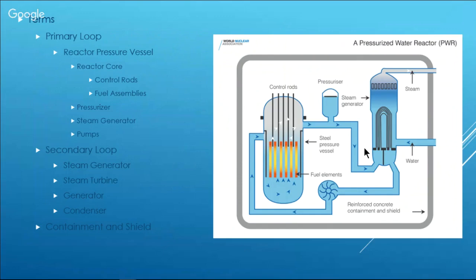So let's say, for example, you have a particular set of control rod positions. You leave them fixed. When you pull heat by pulling off steam, the material going back into the reactor changes density, you increase the reactions, and you increase the heat coming out of the reactor. So by itself, it's a self-regulating thing. Yes, which is pretty cool, and that's what you want. If you're drawing steam out of this reactor and it's cooling down and it basically doesn't change reactor power, you actually need to make it go to higher power, you have to... how should I say this?